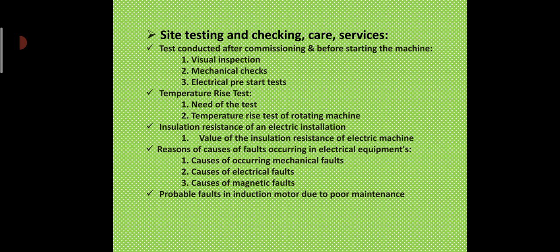If proper maintenance of the starter and control gear is not carried out, the contacts get spoiled. Single phasing may result if one contact does not work properly. There is a possibility of burning of the winding. Magnetic unbalance and vibrations are produced if the air gap between the stator and rotor is not properly maintained. The motor draws excess current if the rotor rubs with the stator while rotating. There is a possibility of accidents if the nuts and bolts on the foundation are not tightened properly. So these are all matters of site testing, checking, care and services.